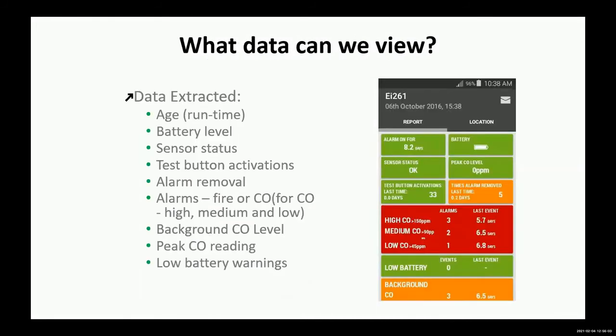So that's the format that you get. We'll have a look at it in a bit more detail and see exactly what data you can extract from that. The age, which is the runtime of the unit, the time the unit has been on the ceiling. The battery level, the battery status of the unit. The sensor status, we monitor for open and short circuits within the sensor itself. Then you've got your peak level of carbon monoxide if it was present. So it gives you the ppm of carbon monoxide up to a level of 999, just going through the 3 digits.